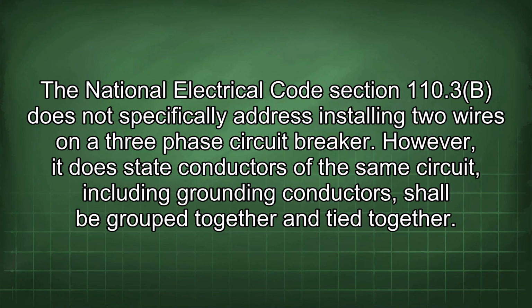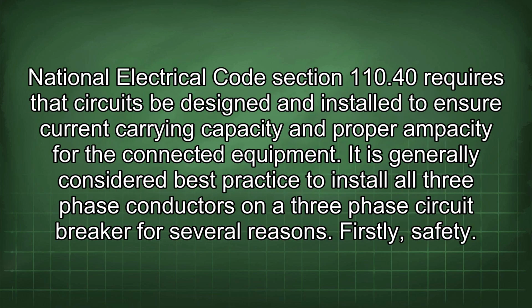National Electrical Code Section 110.3b does not specifically address installing two wires on a three-phase circuit breaker. However, it does state conductors of the same circuit, including grounding conductors, shall be grouped and tied together. NEC Section 110.40 requires that circuits be designed and installed to ensure current carrying capacity and proper ampacity for the connected equipment.